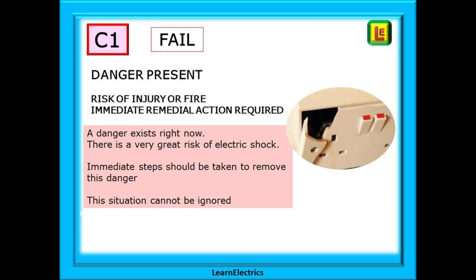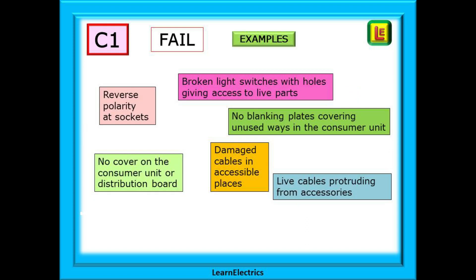Let's look at some of these codes. A C1 is an automatic fail and will make the installation unsatisfactory. Danger is present — there is a risk of injury or of fire and immediate remedial action is required. In other words, a danger exists right now. There is a very great risk of electric shock and steps need to be taken to remove the danger right now. It might be as simple as disconnecting the circuit. This situation cannot be ignored. On this page we've shown some of the things that may trigger a C1 observation.